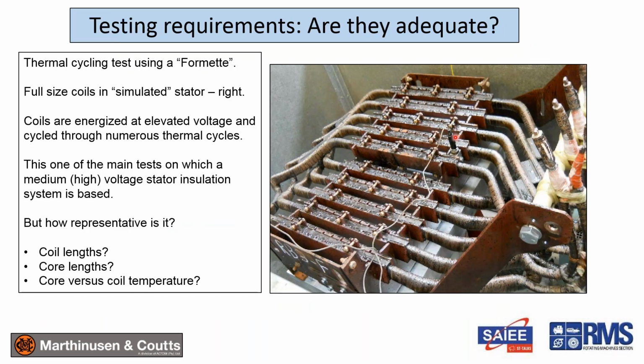So here we look at the Formette, and there should be something very interesting that you notice about this: how representative is it? The coil length is shorter, typically. The core length is also shorter. And there's the core versus the coil temperature. Now, in a real machine, when that machine starts up, you get a very different temperature between the stator coil and the core. In these thermal endurance tests, everything's heated up together. I think most of them use the steel portions, the simulated slot portions, to actually heat up the coil. So your core does not heat up and expand in the same fashion as in the test as it does in the real machine.